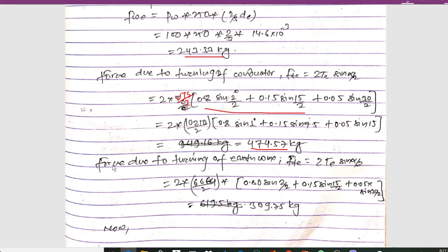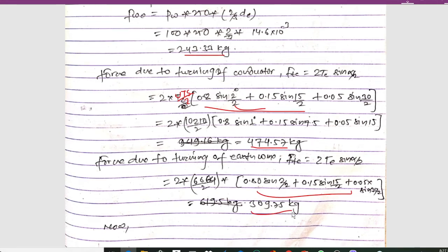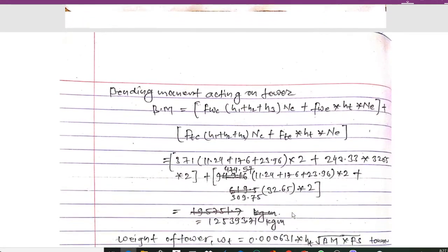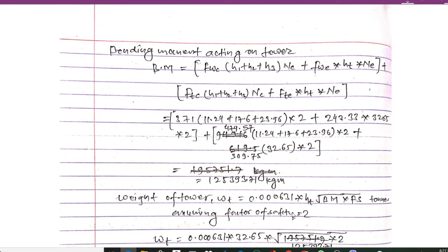Similarly, force due to turning of earth wire (FTE) is: FTE = 2TE × sin(α/2), where TE = UTS/2. Using the same tower type distribution, the calculated value is FTE = 309.75 kg.